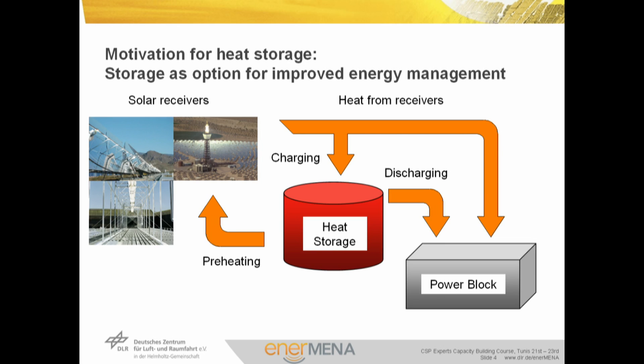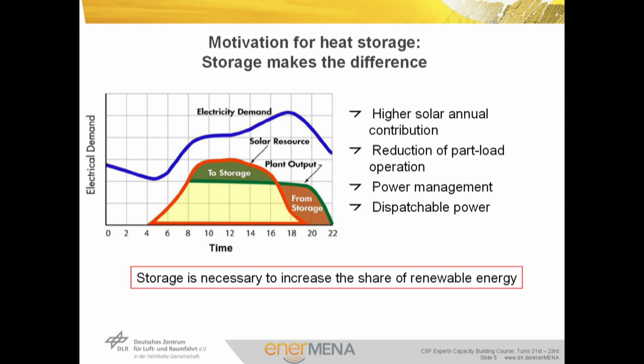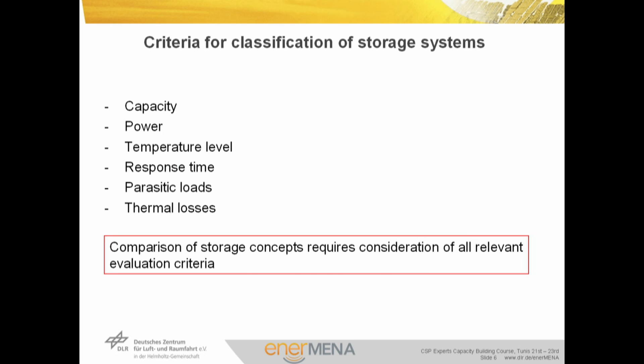Storage units increase the efficiency of energy systems by compensating the temporal mismatch between available energy and demand. Storage represents an additional option for energy management. The option to integrate storage capacity locally is a unique feature of CSP technology. Adding storage capacity increases annual solar energy production, improves power cycle efficiency by avoiding part-load behavior, and allows adaptation of electricity production to demand. Dispatchability is mandatory if the share of renewable energies is to be increased.